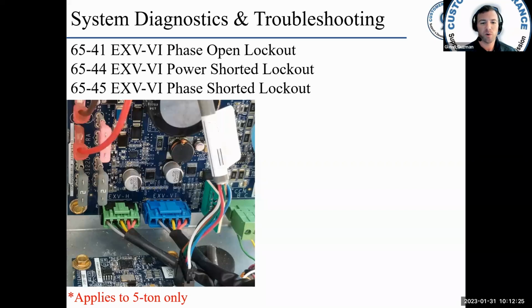6541, 6544, and 6545 all have to do with the vapor injection circuit, the EXV. Okay, and this applies to the 5 tons only. Only the 5 tons have the vapor injection circuit. The EXV is required to operate the vapor injection circuit when it's used in high demand situations, such as high ambient cooling or low ambient heating. Once a day, the EXV VI will test itself by operating to a known position. The valve does not have the capability to provide feedback, just like the heating EXV.